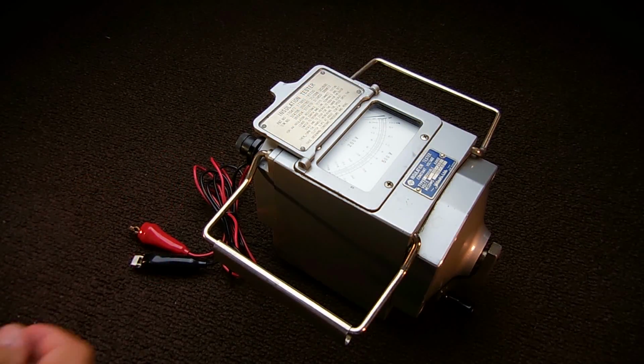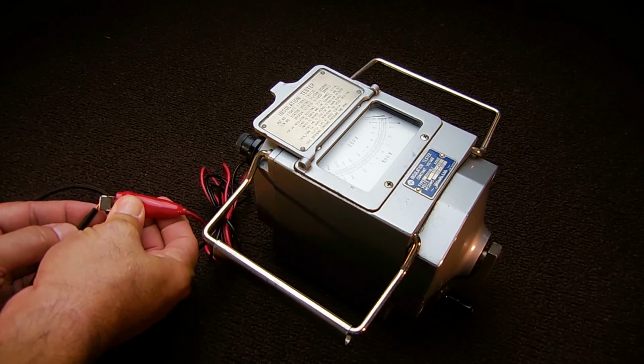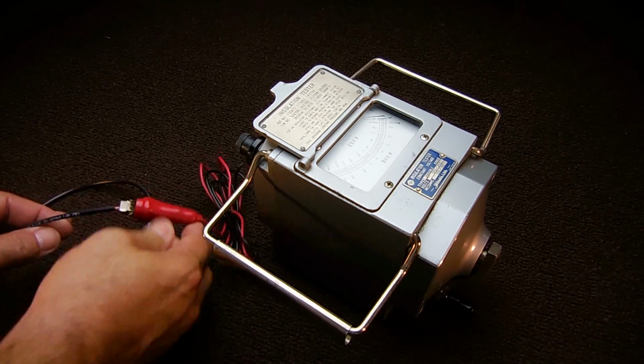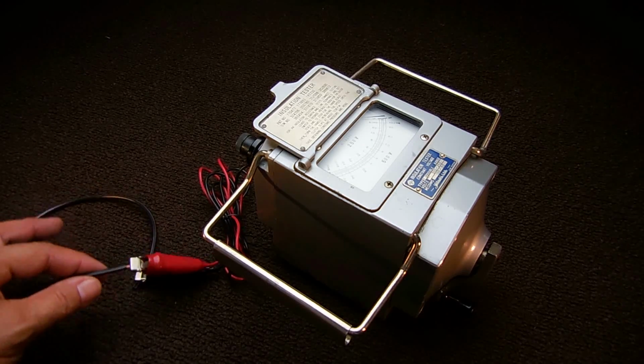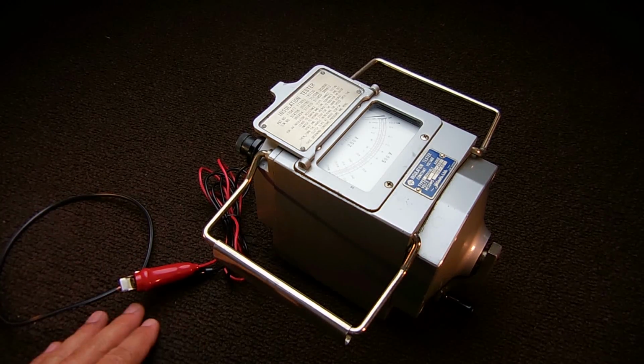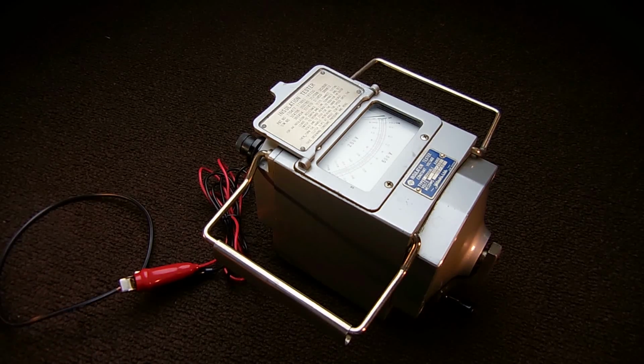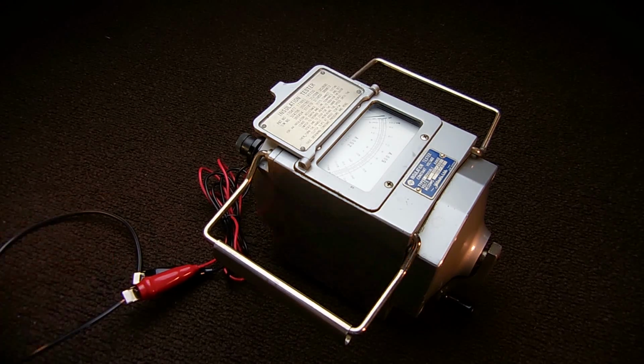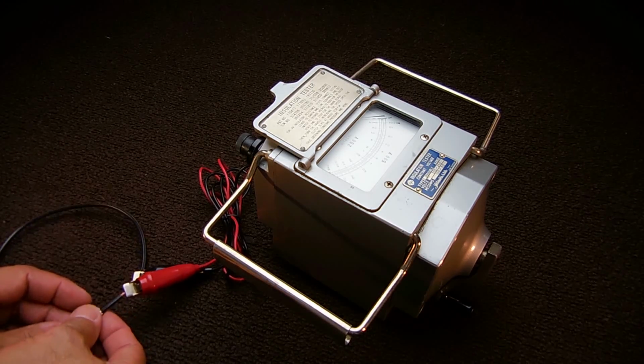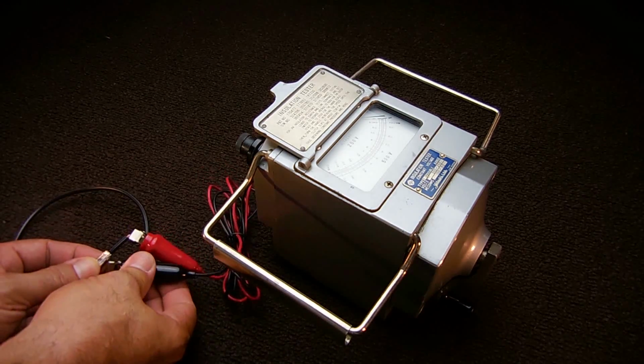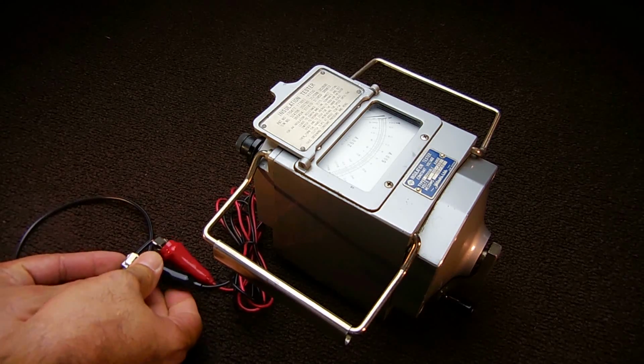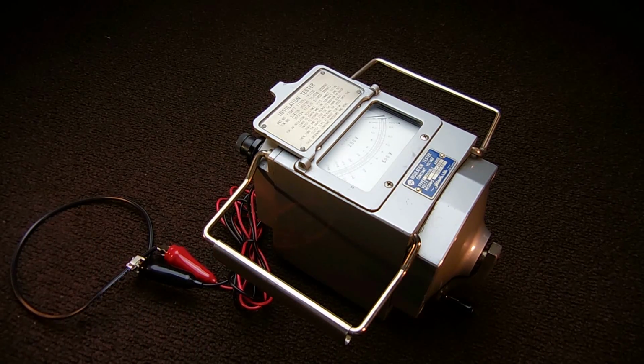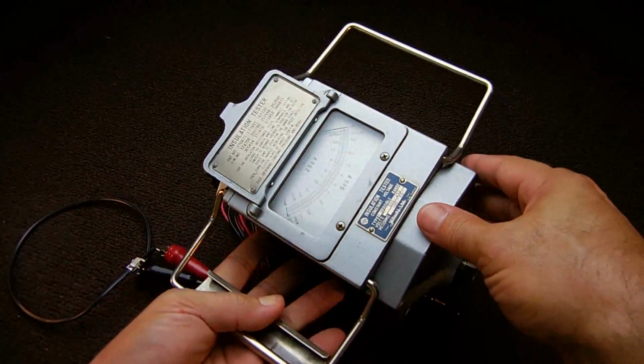I'm going to take one of these, place it on the center conductor, like that. Make sure you do this on a non-conductive surface. You don't want to do this anywhere where it can affect the reading. So be careful when you do the reading, always on a non-conductive surface. Now I could just clamp this on the wire, but I don't want to damage the insulation, so I'm going to put a little piece of foil on the outside and then clamp it like that. Okay? Now I'm going to tilt this so you can see it.